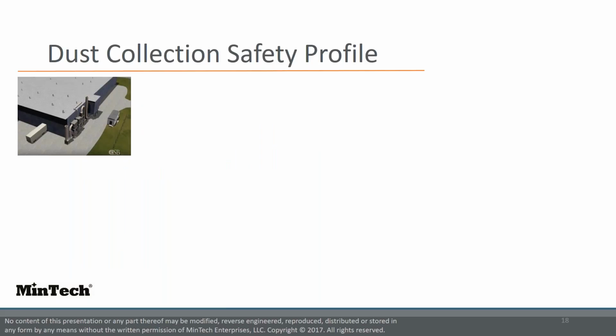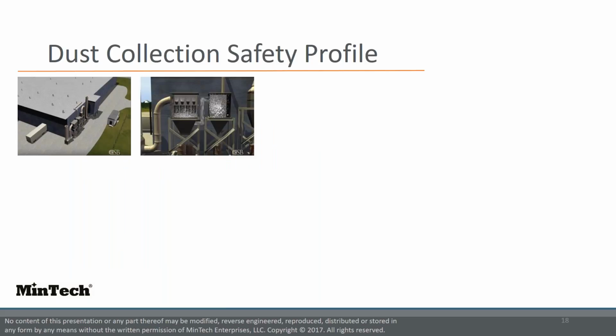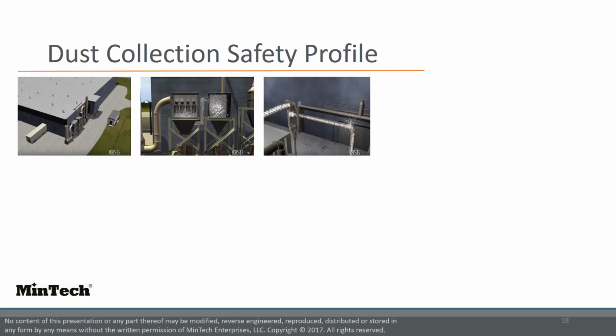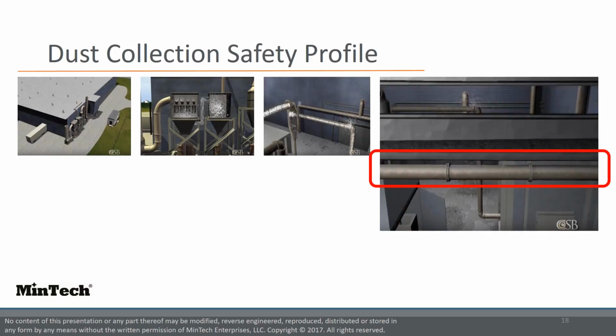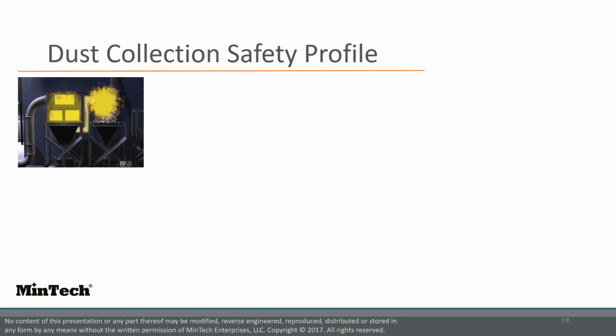Let's take a look at a typical progression of a dust collector explosion. Here's a typical setup with a dust collector positioned outside of an industrial plant. Combustible dusts are carried from exhaust hoods to the drop box and into the dust collector. Dust builds up inside of the ductwork and often leaks from the ductwork where it builds up on surrounding surfaces. This picture highlights how combustible dust builds up on a horizontal surface like beams, ledges, pipes, and equipment.